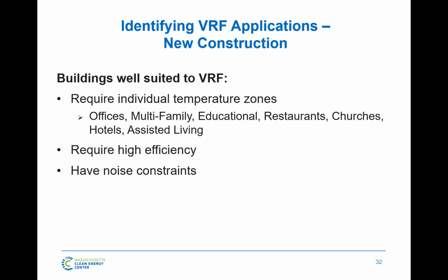Once you start getting into buildings that require zoning, such as office buildings, multifamily residential, all sorts of educational, restaurants, hotels, assisted living, whatever that may be, those are all buildings where there's potential to need a high level of individual temperature control or zoning. Like JS said, if you're in a hotel, you can't be in a room and say, well, I'm too hot in here because the average of all the other people around me want to be warmer too. No, if you're paying to stay in a hotel, you want to be at the temperature you put on the thermostat, and those are the situations where VRF really starts to shine. And this is what we're seeing in all sorts of buildings, even buildings like this. Buildings are becoming very mixed use.